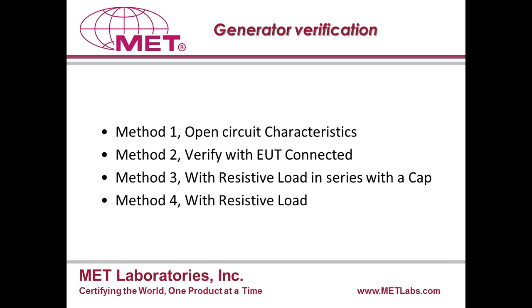So moving along, method number 3 is a resistive load in series with a capacitance, and the standard specifies using a 1700 microfarad capacitor. Again, using this method leads to serious problems. The waveform drastically gets cluttered, and you do not get a real picture of what the output of your generator is. The third method, sorry, my apologies.